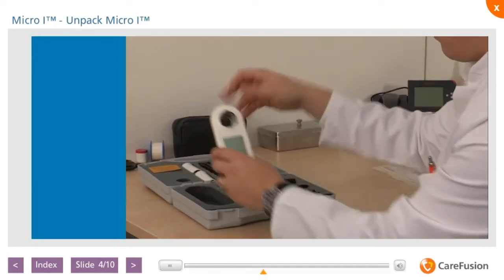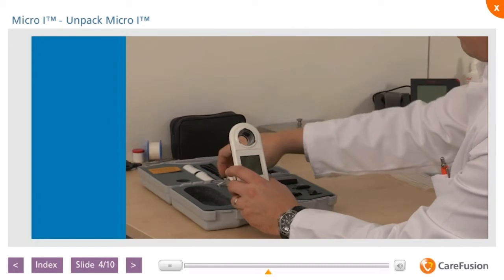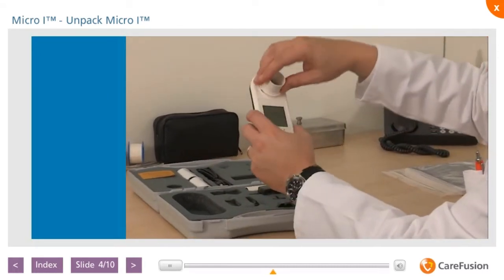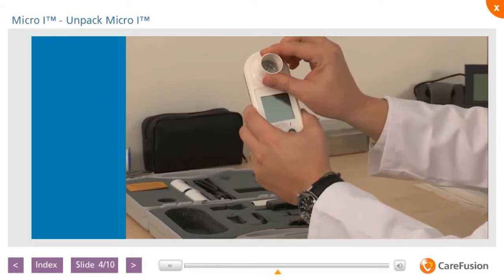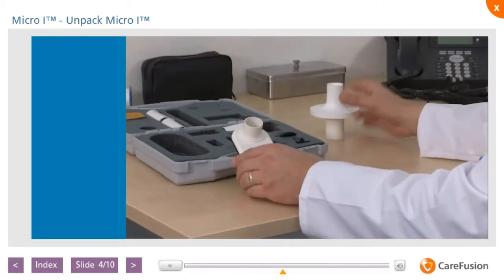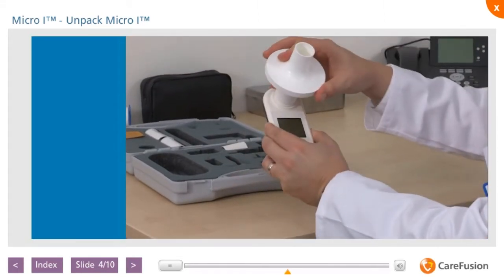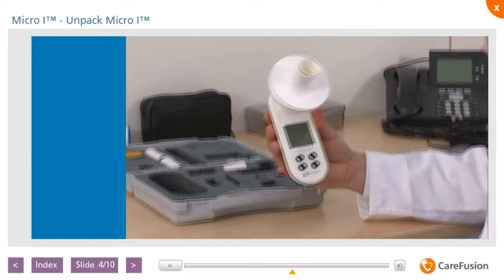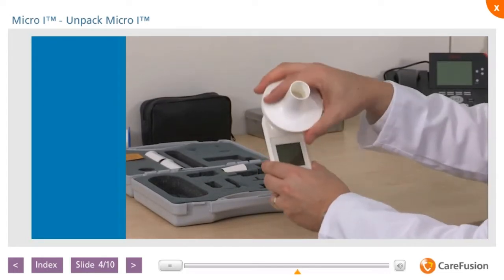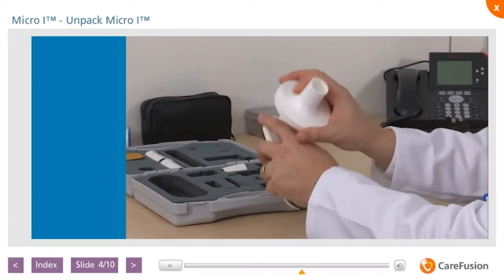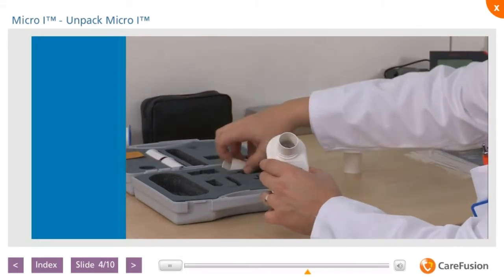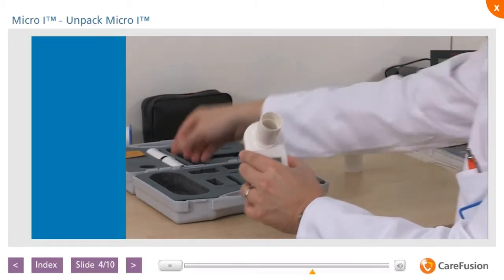To connect the turbine transducer to the Micro I, simply slide it into the transducer mount and twist it into place. The spirometer can be used with either a bacterial filter or alternatively with a disposable mouthpiece, in which case the mouthpiece adapter should be connected onto the turbine and then the mouthpiece placed into the adapter as shown.